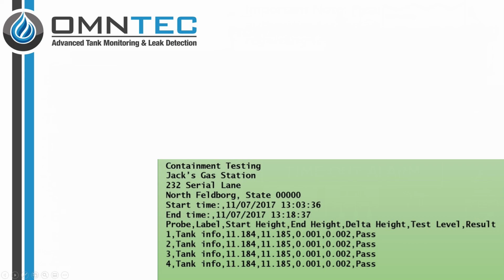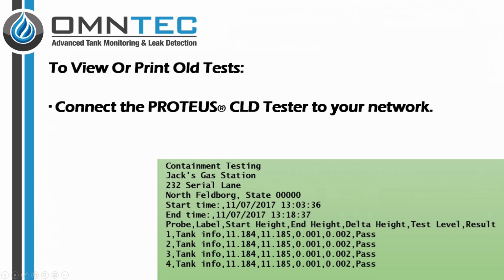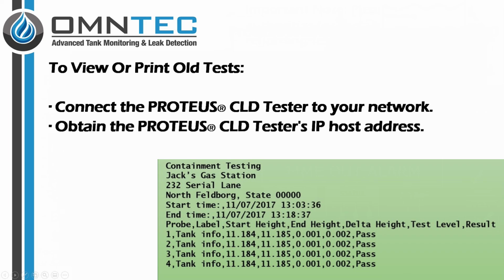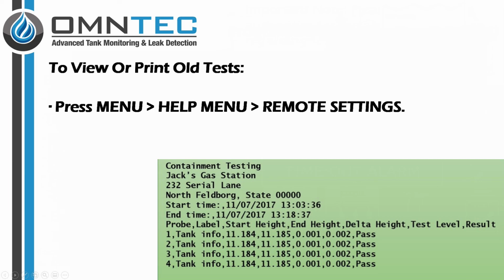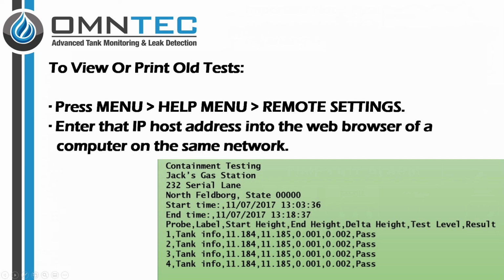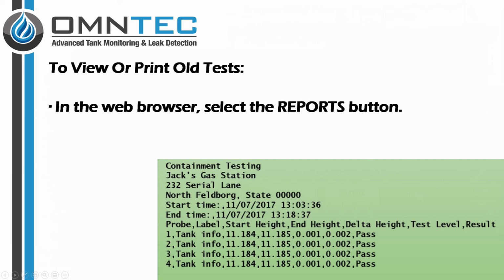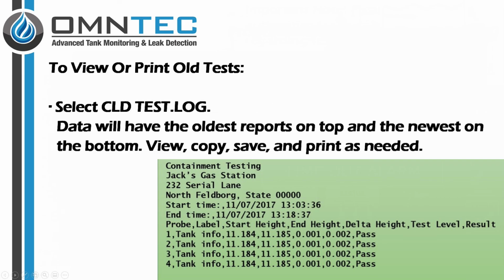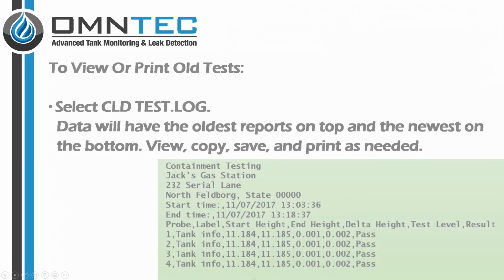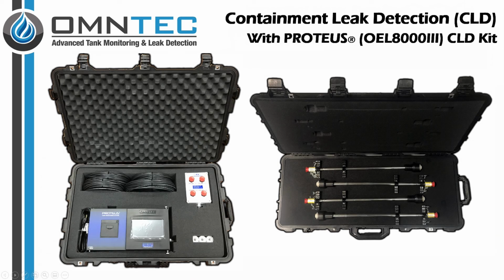Reports are backed up in a comma-delimited format on the SD card. To view and print old tests, connect the Proteus CLD tester to your network. Obtain the Proteus CLD tester's IP host address. Press Menu, then Help menu, then Remote Settings. Enter that IP host address into the web browser of a computer on the same network. In the web browser, select the Reports button. Select cldtest.log. Data will have the oldest reports on top and the newest on the bottom. You can then view, copy, save, and print as needed. This completes the presentation for setting up, programming, and performing a sump test using a Proteus containment leak detection kit.